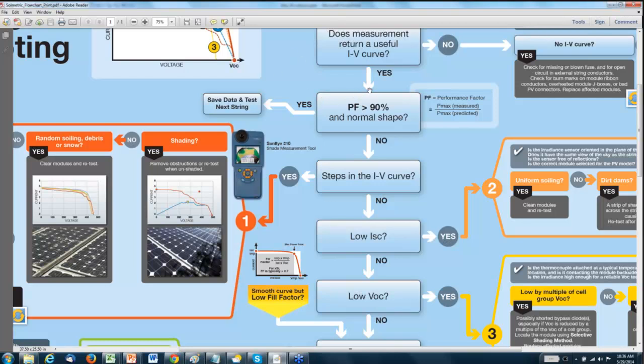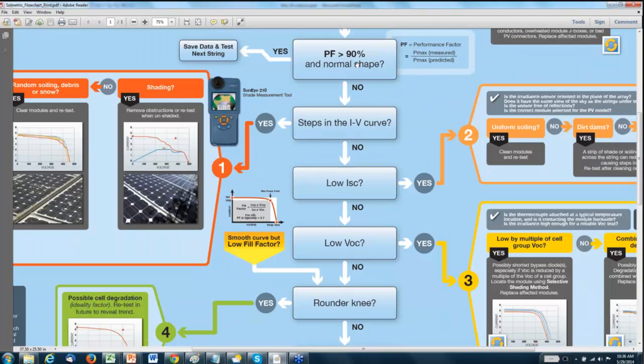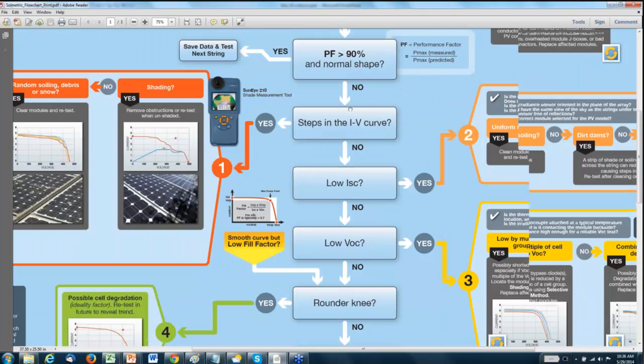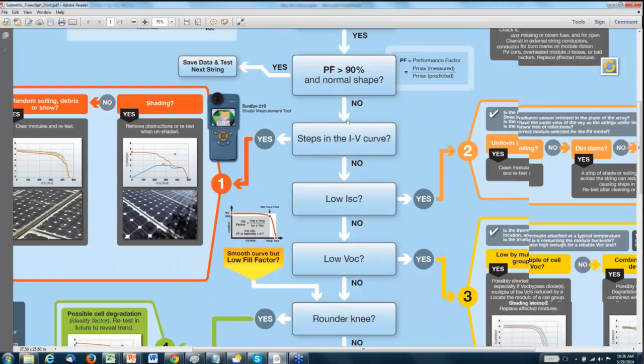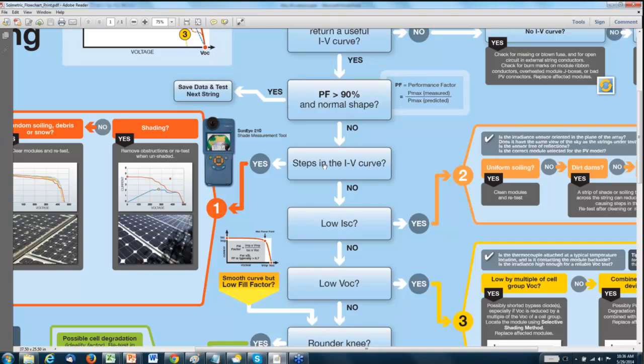or recommissioning it. However, if your performance factor is low or you're not a normal curve shape, then you exit that box with the no and drop down to check if there are steps in the IV curve. And the reason we put that first is that quite often steps in the curve are caused by shading or debris or litter or soiling, and that's something you can do something about. And it tends to mask the performance pretty well. So you want to take care of this first.